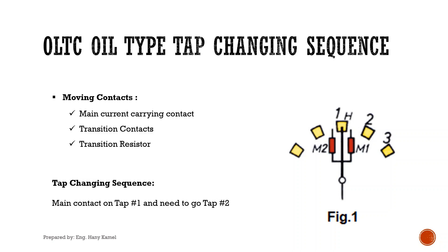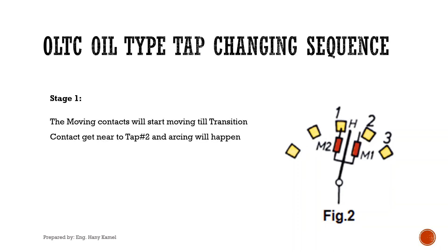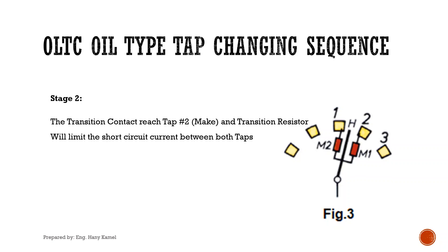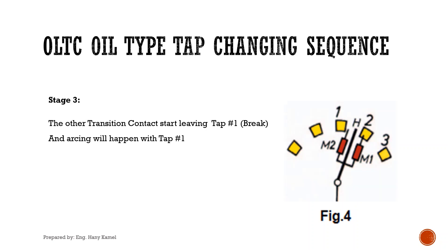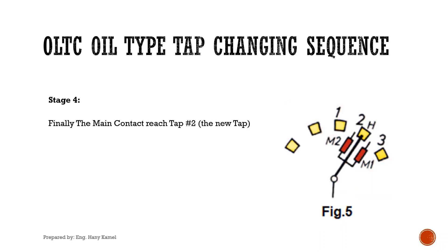Now we will take an example of how tap changing happens — the sequence of operation for the moving contacts. The tap is number 1 and we need to shift the moving contact to tap number 2. Stage 1: the moving contacts start moving until the transition contact gets near tap number 2; arcing will happen between them. Stage 2: the transition contact reaches tap number 2 — make — and the transition resistor limits the short circuit current between both taps. Stage 3: the other transition contact starts leaving tap number 1 — break — and arcing will happen with tap number 1. Stage 4: finally, the main contact reaches tap number 2.